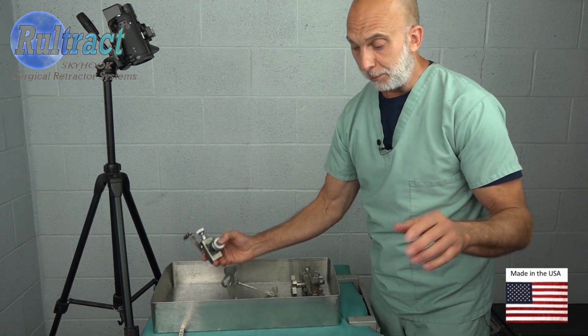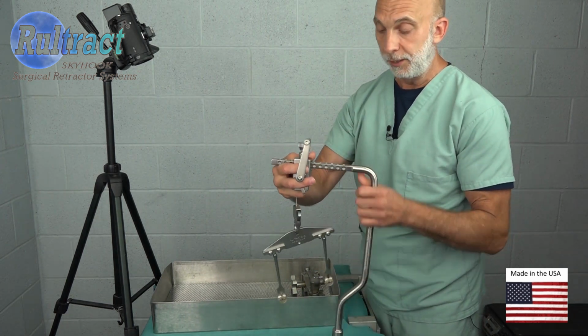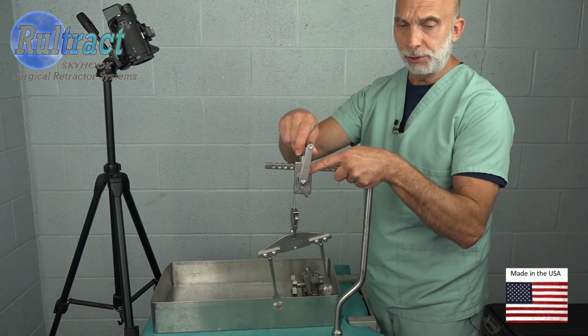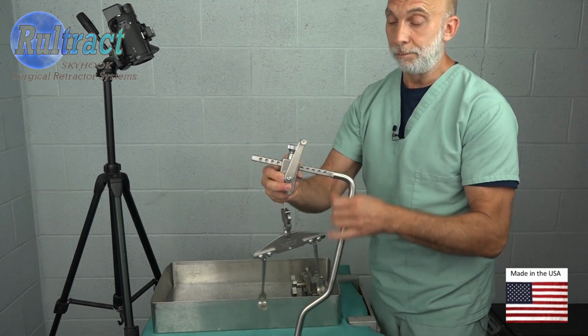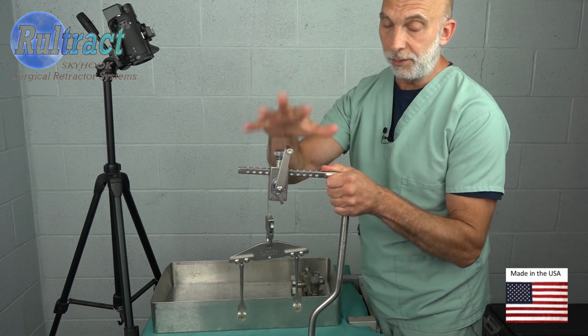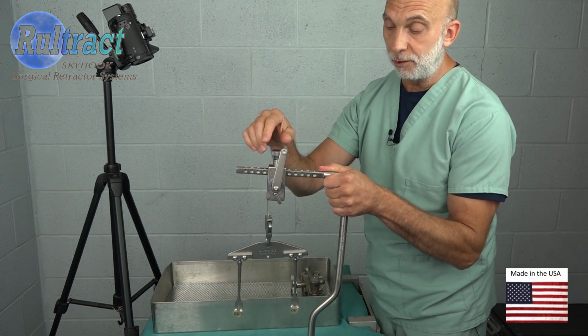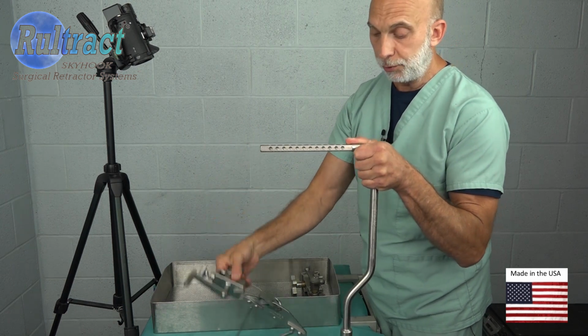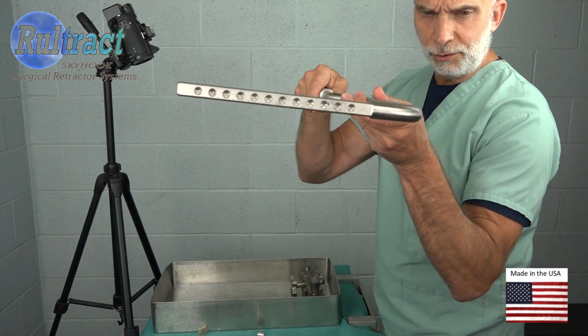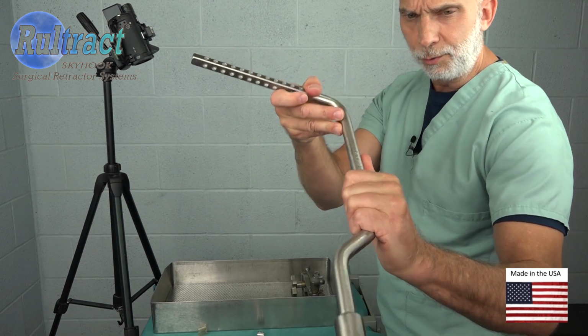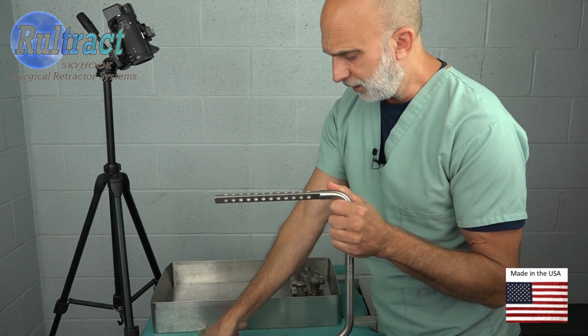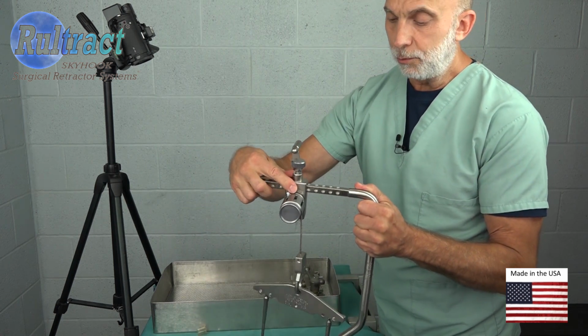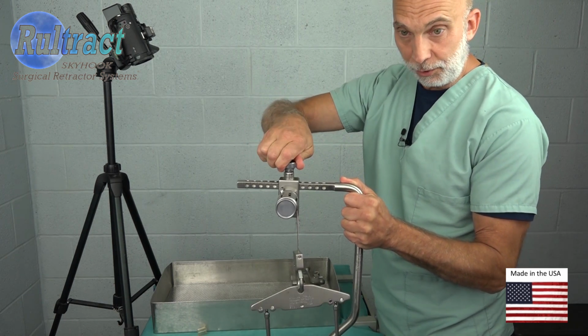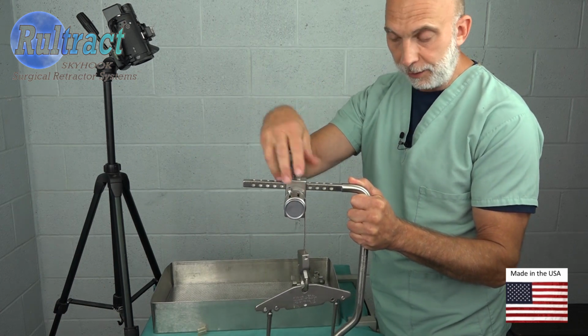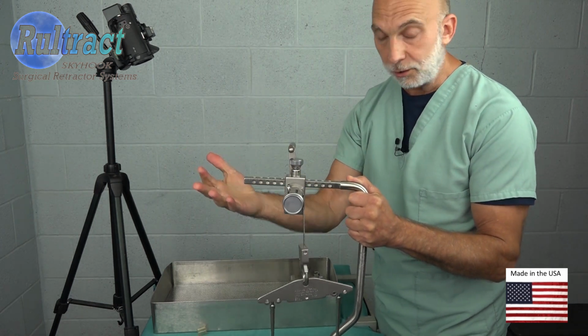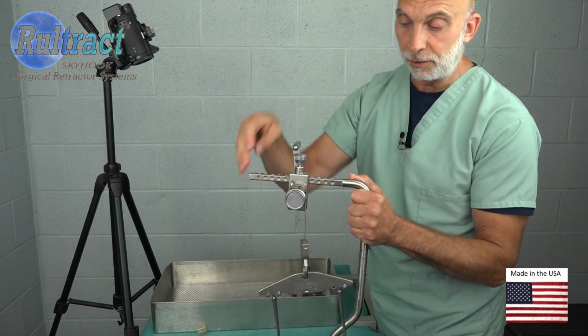The next thing is, it's also brought to my attention that there are times when SPD is being asked to put the ratchet assembly onto the top post for sterilization. So then it would come into the OR like this. Again, our sterilization parameters have not been tested with these two pieces together, so we cannot say that it is okay to do that. Reason being here is your top post has what we refer to as detents, and you can see those detents go all the way around these top posts. So if you put this ratchet assembly onto that top post and then you tighten your lock knob down into a detent so it doesn't fall off, we cannot be certain that inside this area down into that detent is going to be sterile, because again, our sterilization parameters are not tested for that. So these cannot be together for sterilization.